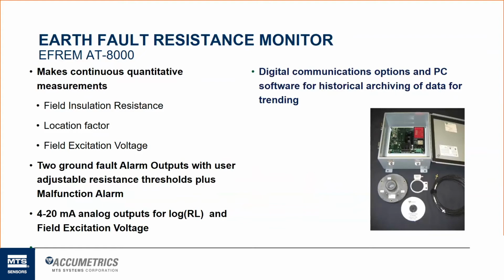We also offer a malfunction alarm. Again, the 2 ground fault alarm thresholds and the malfunction alarm are those Form C contact relays, normally open, normally closed. The malfunction alarm is a normally closed contact. The reason we do that is because if the EFREM system loses power, it will open that alarm and let them know that there is a problem with the telemetry system.